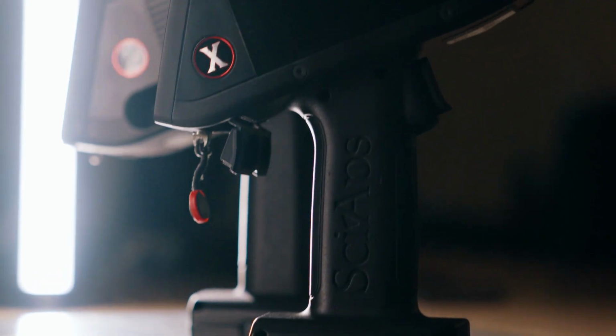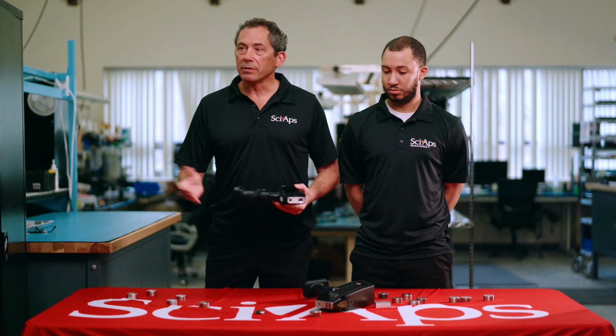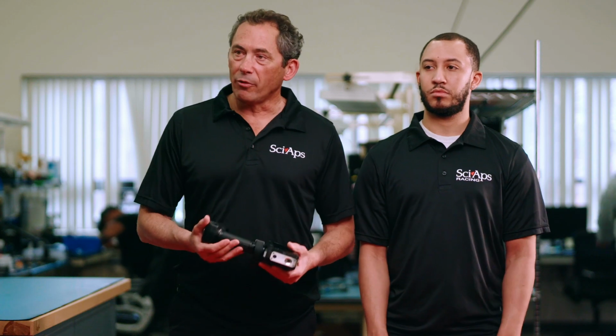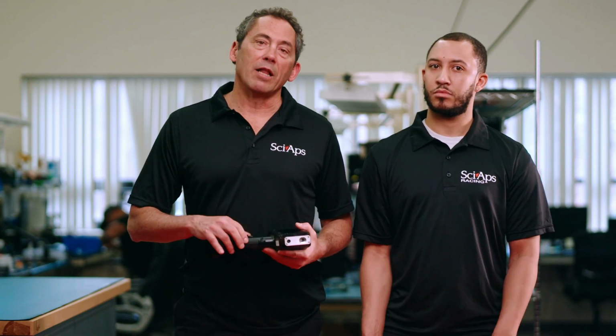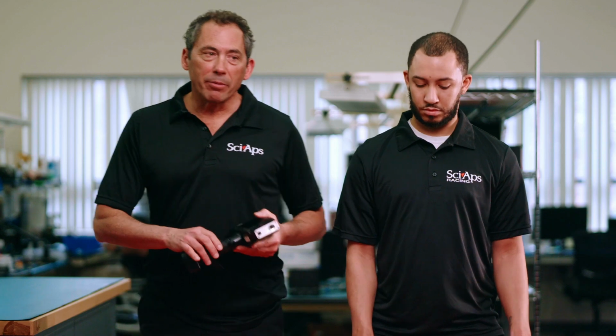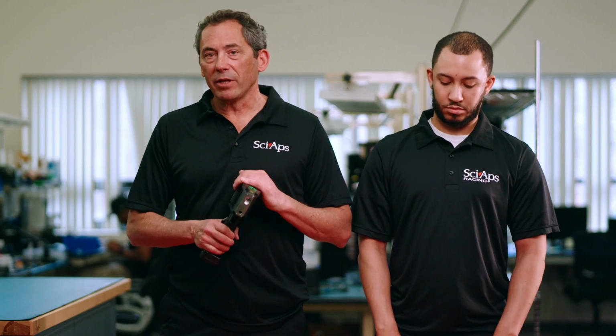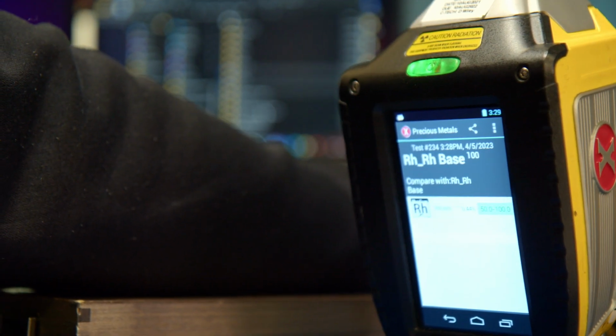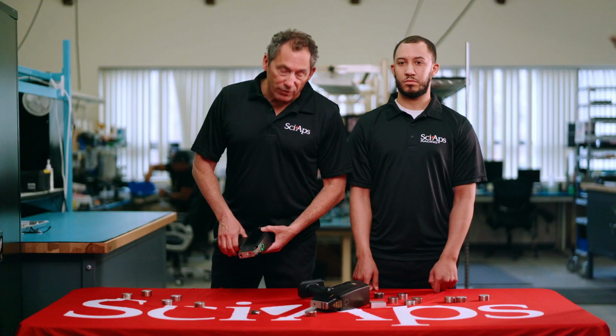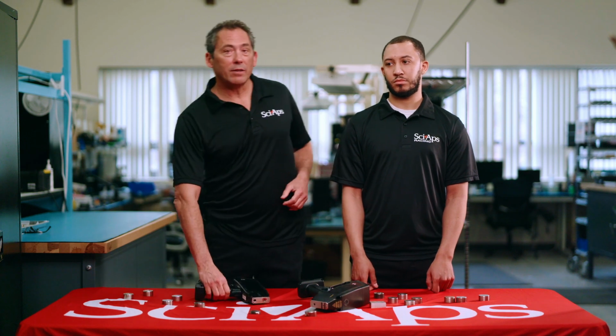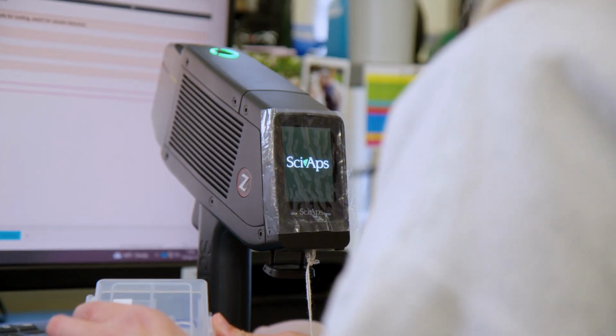Right. That's our goal. So XRF repair, if it's not something that requires recalibration, then it's probably done in a day. If it requires recalibration, it depends on what it is we're calibrating. If it's an alloy calibration, that's probably an extra day. But if it's something like a soil or a ROHS type of calibration, that might be a couple of days. So we should be able to turn these things around in 1 to 3 days, depending on the actual problem and the amount of calibrating it requires. In terms of LIBS, I have to defer to my expert here, Jamal. It wouldn't be too much of a difference. It really depends on what's wrong with the unit.